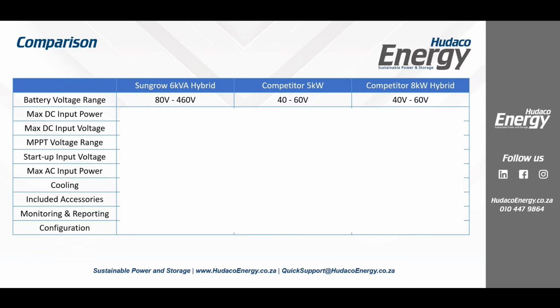Max AC input power. Okay, remember we spoke about this architecture and why it's so critical that we do. Here, 13 kVA. I can run all of my backup loads and I can charge my batteries off grid, even if I have no PV. Here, maybe I can charge my batteries, or maybe I can run load. I have to wait, or if I'm running load, maybe I can't charge my batteries as well at the same time. So it's not even a contest, right? The fact that I could bring 13 kilowatts either from PV or from grid to do what I need to do changes the dynamic totally in terms of how many I need on site.